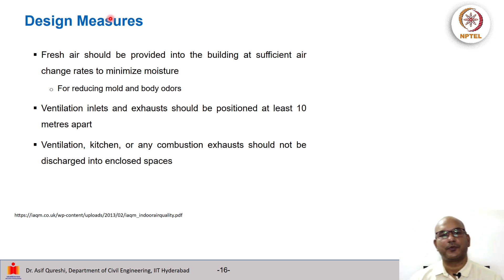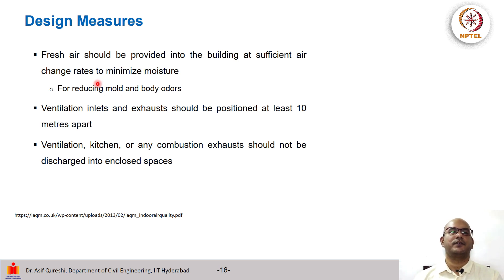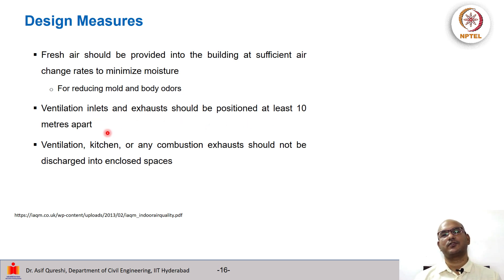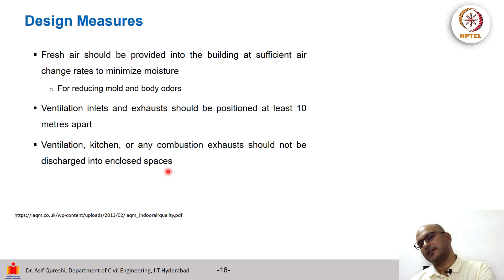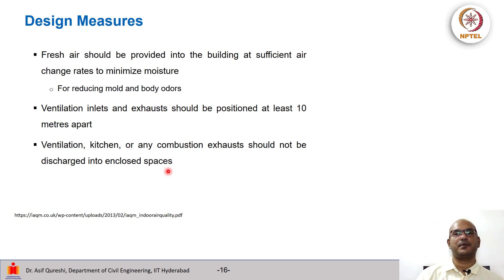Good design measures can also be adopted. For example, fresh air can be provided into the building at sufficient air change rates to minimize moisture build-up, which in turn will reduce mold and body odours. Ventilation inlets and exhausts should be positioned at least 10 meters apart, otherwise whatever exhaust comes out immediately goes back in. Kitchen or any combustion exhaust should not be discharged into an enclosed space, because that would mean sucking polluted air from one place and putting it in another. Exhaust should go out where the pollution can be diluted.